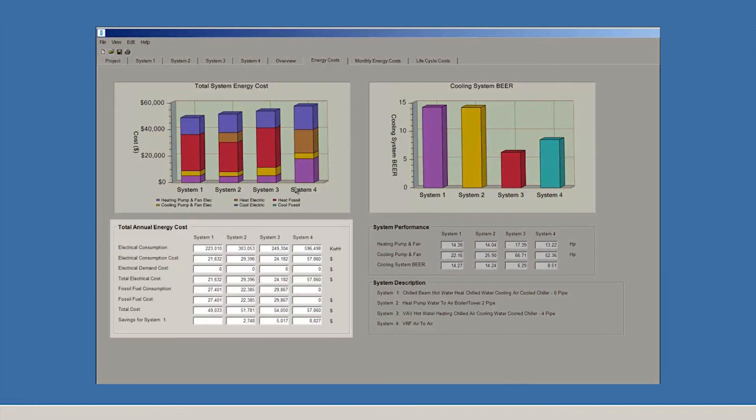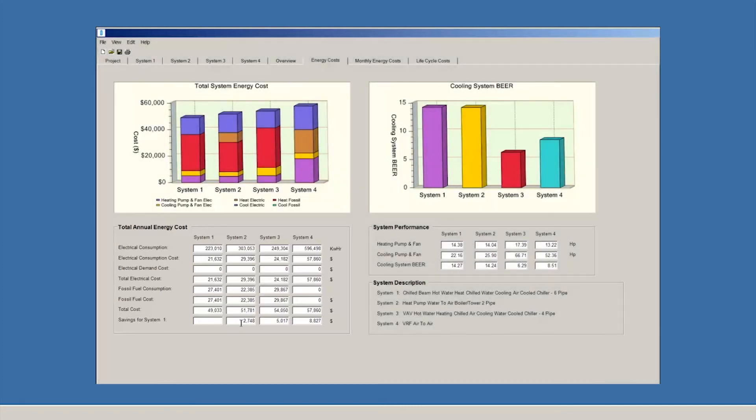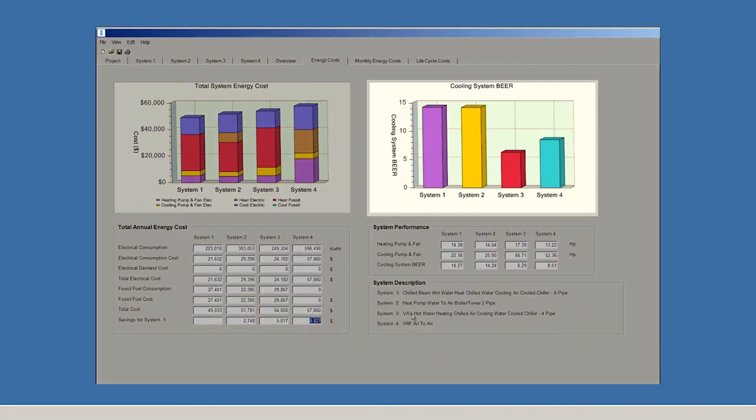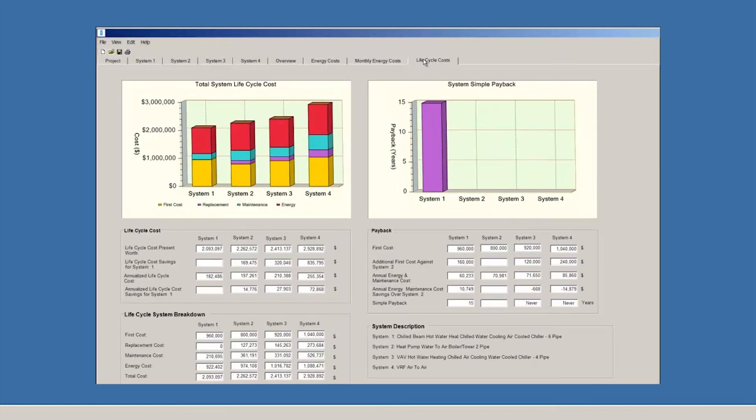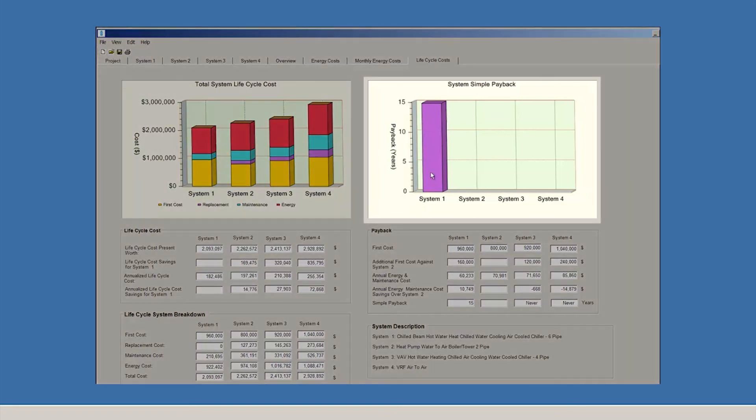The wizard feature also serves up data on estimated energy costs and life cycle costs based on defaults from the System Wizard. Right at the bottom, on the left-hand column, we can see that BEST has crunched the numbers and has a comparison of energy savings for each system. In the upper right-hand corner, we can see the Beer Ratings for each system, the Building Energy Efficiency Ratio, as opposed to the Equipment Energy Efficiency Ratio. This is essentially a System IEER that we call the Building Energy Efficiency Ratio. We can also go to the Life Cycle Costs screen and view the life cycle costs of the four different systems. The total estimated costs are right at the bottom. In the upper right-hand corner, we can see the payback of each system over the lowest first cost.